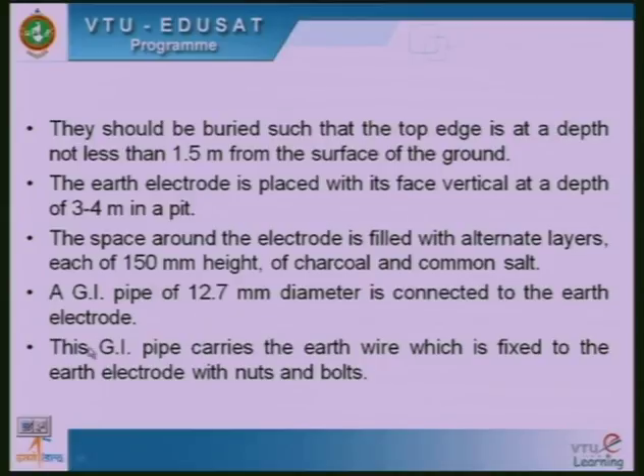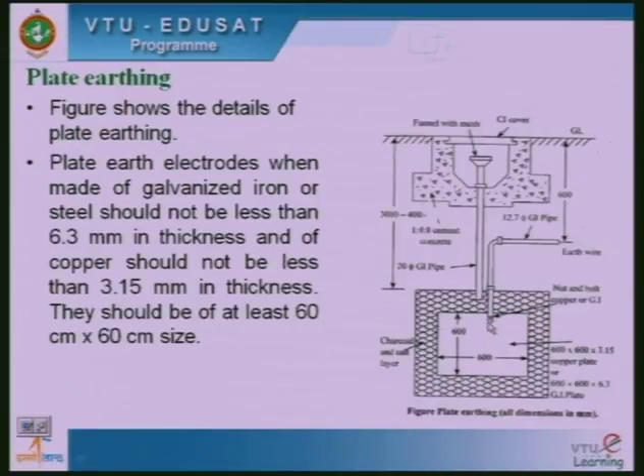.7 diameter. This GI pipe carries the earth wire, which is fixed to the earth electrode with nuts and bolts. So, that also you can see here, I will be connecting here. Okay. So, the wire will be connected to this plate here and it passes through this earth wire, through this.